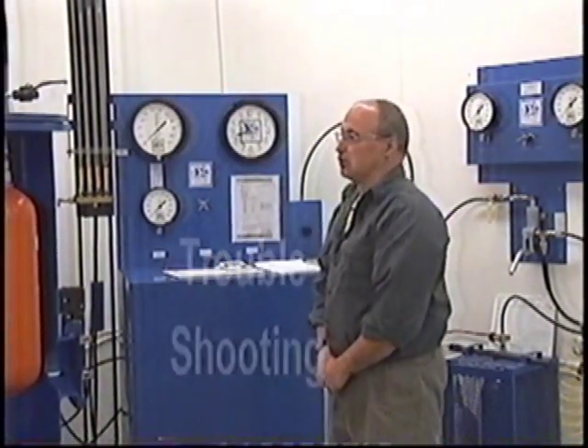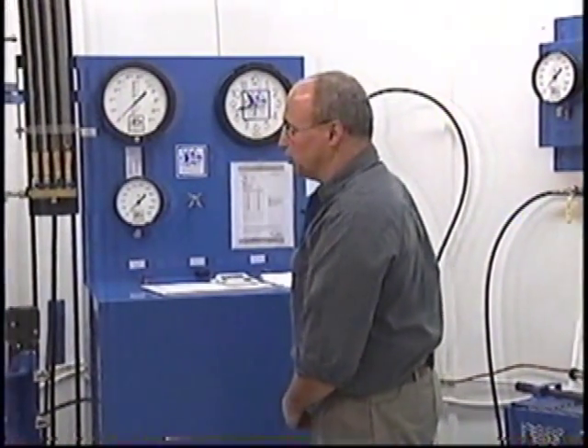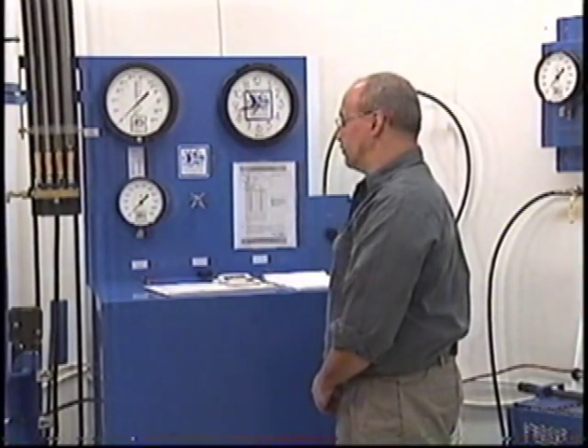All troubleshooting on your hydrostatic test machine should be done with your calibrated cylinder loaded into the water jacket. The calibrated cylinder must be used as it is the only stable cylinder that you have.